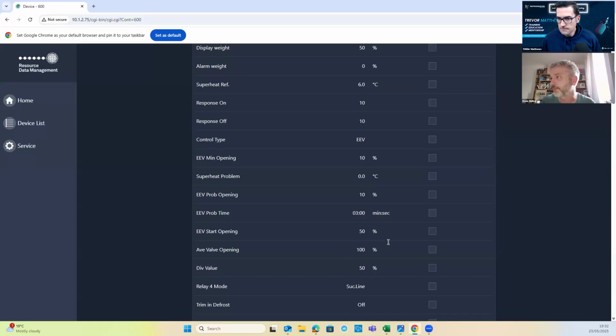Other parameters for the valve right here. So if I see a superheat problem, what percentage am I going to go to? Now, the reason they keep 10% in there is for if you're not using a transducer. If you're using a probe, it wants to keep trickling some refrigerant through it, so you've got a chance of rectifying itself. If you're using a transducer and it sees a superheat fault, you can set that to 0, not a problem. And it'll then wait for its problem time, and then it'll try and start the valve up again.